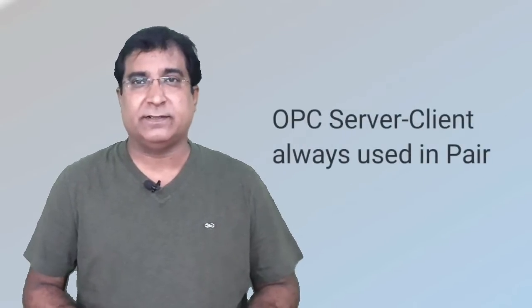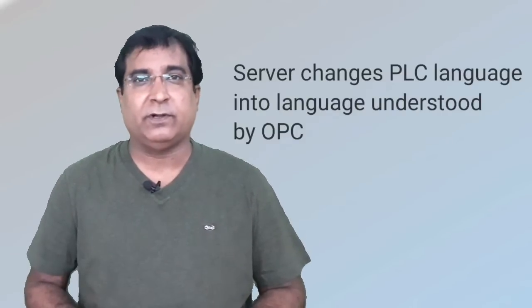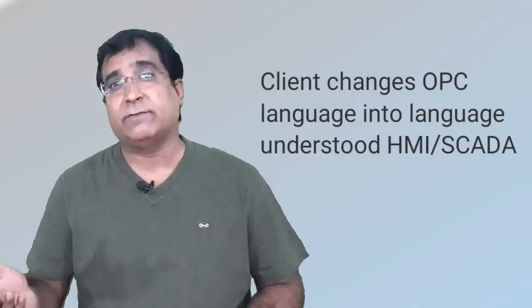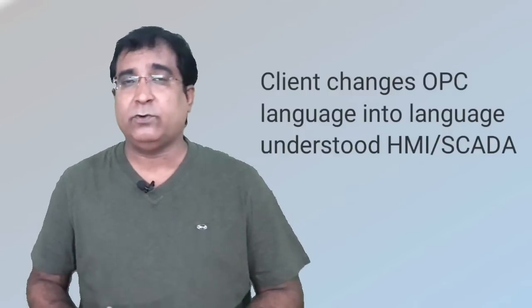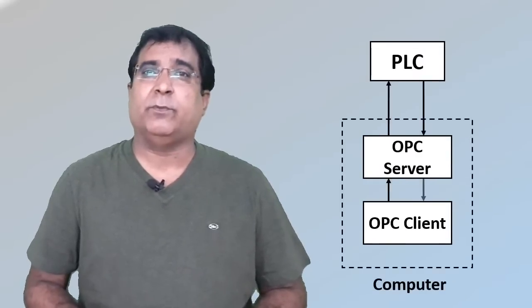Basically, this OPC standard was developed for Windows OS to access different hardware and is generally used in OPC server-client pairs. It means the client sends data requests and the server has to serve the request. OPC Server is a kind of program which converts PLC communication protocol to OPC protocol, and then again OPC Client converts back this OPC protocol to HMI SCADA application format or operator format.